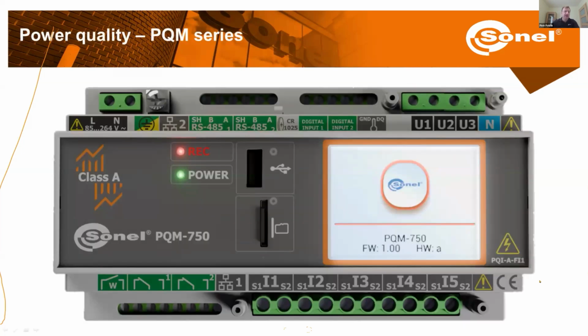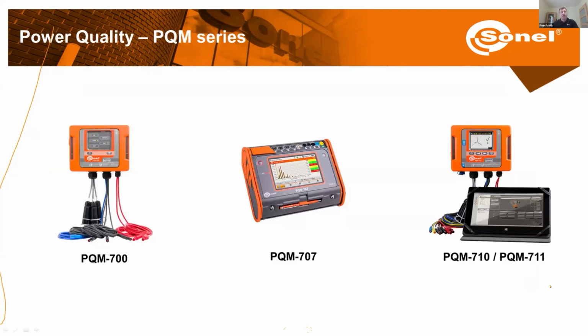Now let's look a little bit at diagnostics. First of all, what comes to our minds is power quality. Here, at Sonel, we have two groups of meters. One, like the PQM 750 over here, is a permanently installed meter. So we can install it somewhere, for example near a transformer station or on some switchboard which is powering the vehicle chargers. Or we have portable meters, so in case we have some anomaly, we can temporarily connect the meter, record the quality of the power, and later take down the meter and analyze what's going on in our network.